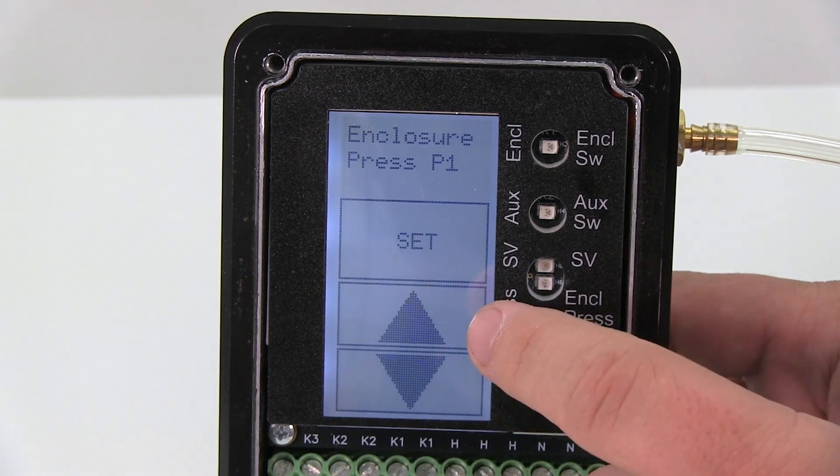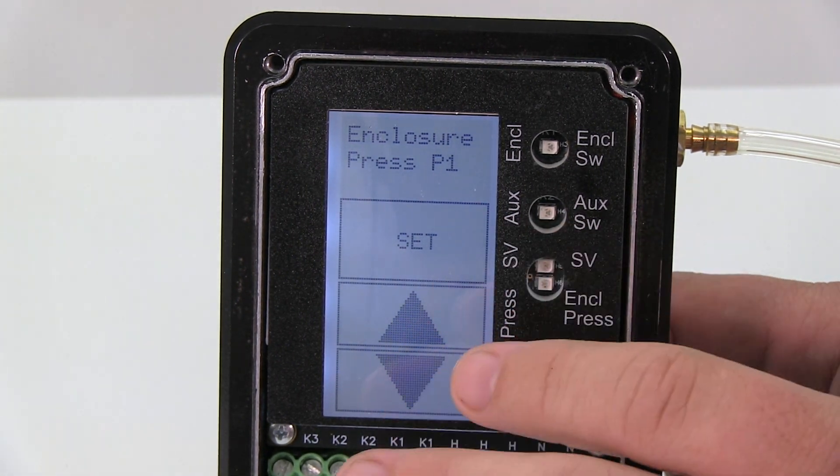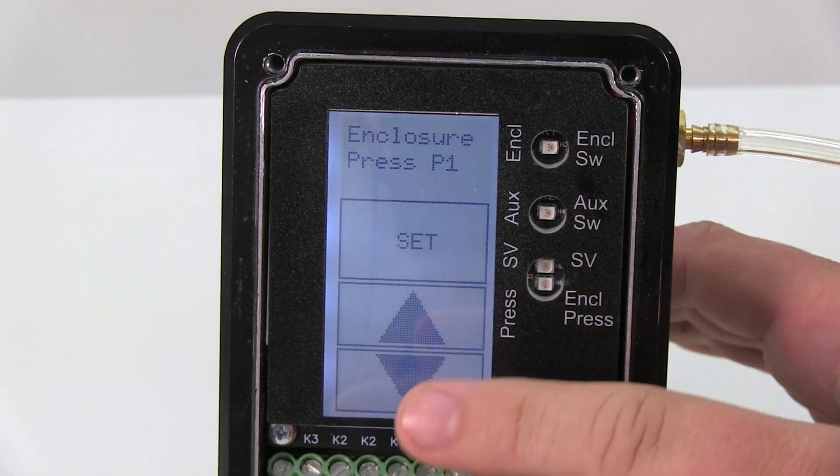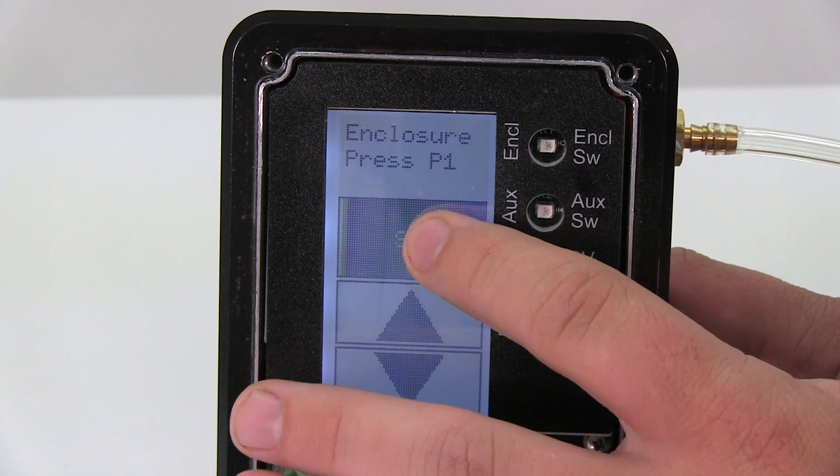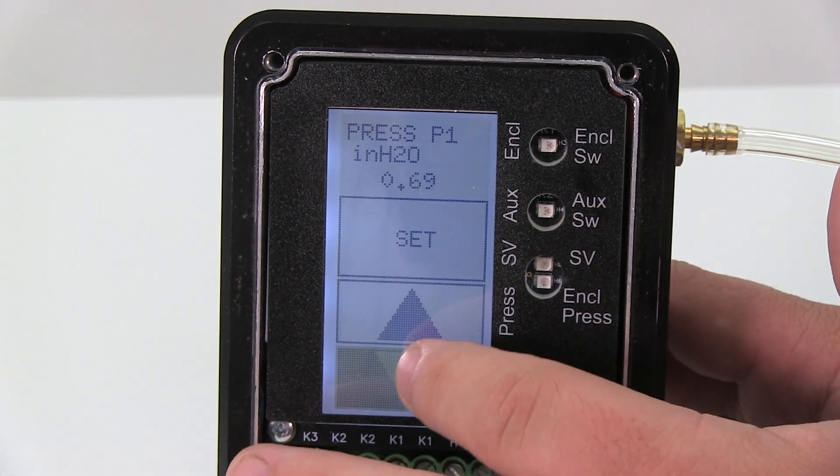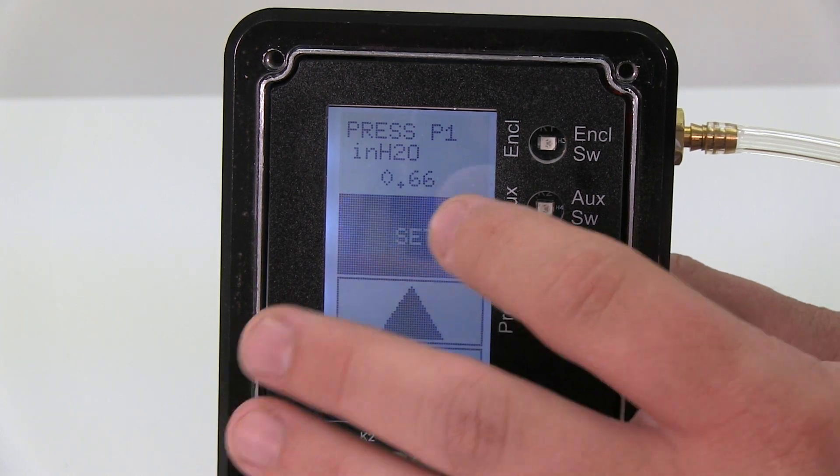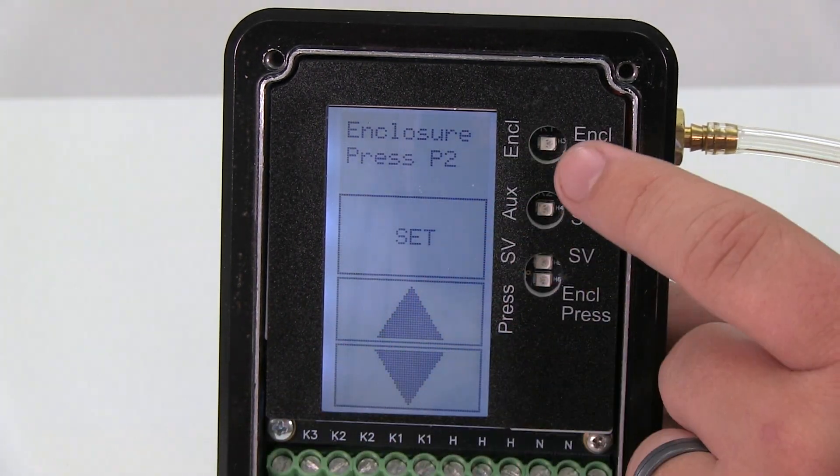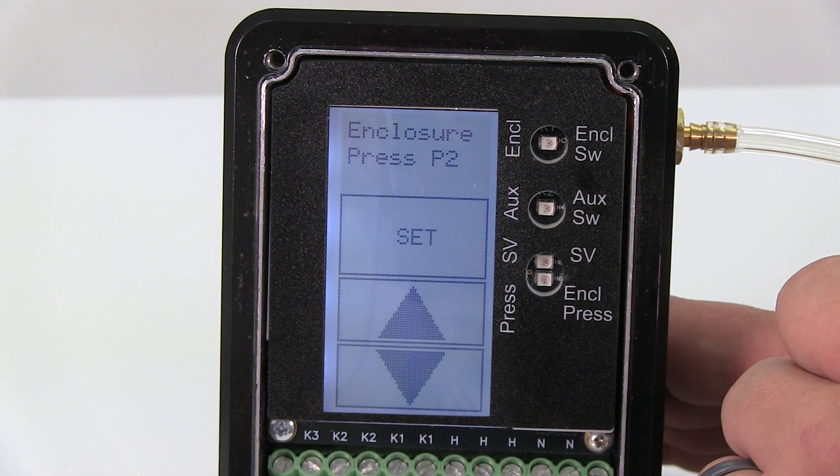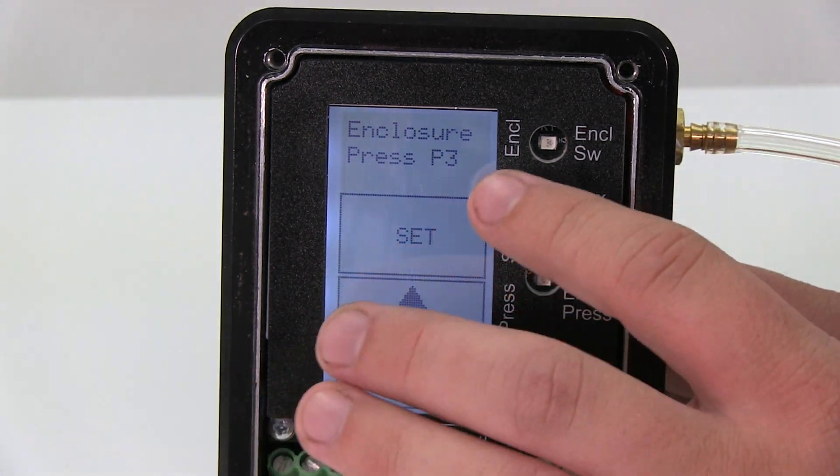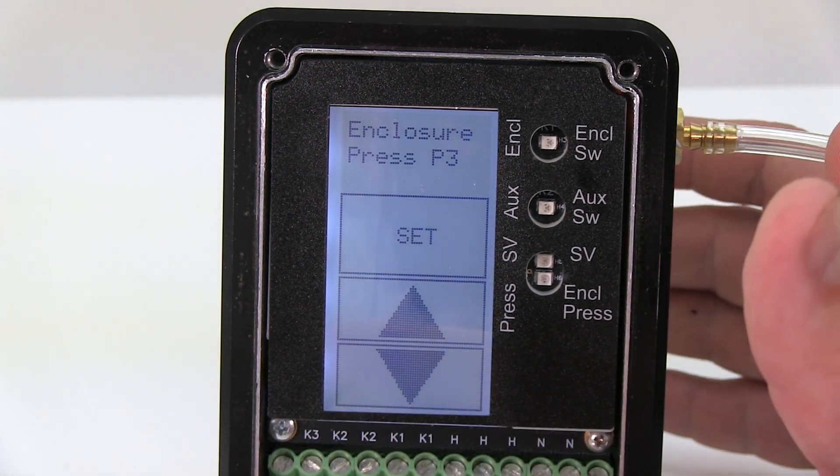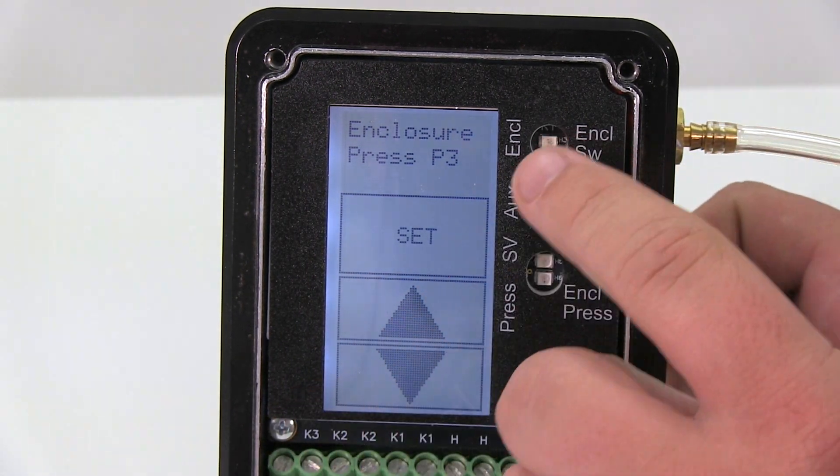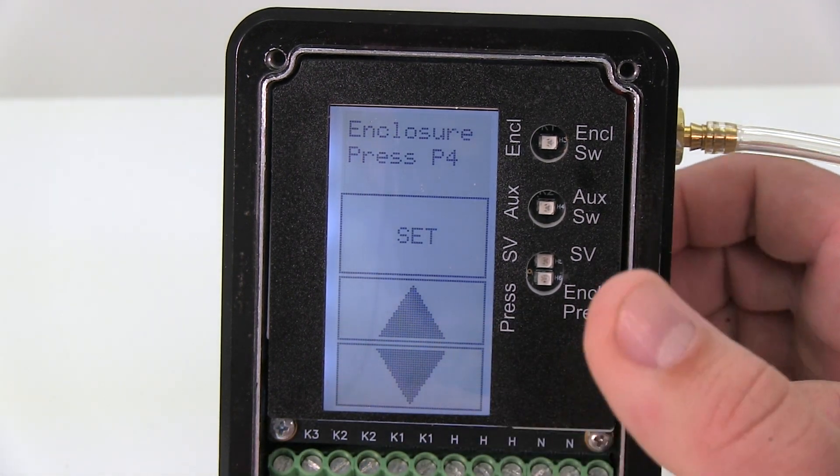The next menu option is the enclosure pressure P1. That's your minimum enclosure set point - so roughly for gas applications, 0.25 inches of water. For this one I had it set for a demo at 0.7 inches, so you can scroll down and set that minimum pressure to whatever you want. Your other pressure settings: P2 is an alarm pressure you can decide to use or not. P3 would be your purging pressure, so whatever pressure you want to be at during your purging cycle. And then P4 is your max pressure - you can set that to a max pressure that you don't want your enclosure to exceed.